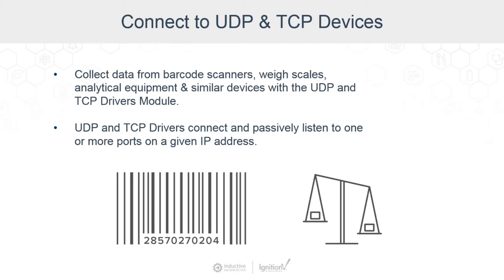Travis, your experience on that? It's important because it's part of integration with all the devices and information you have within a plant, and it's about how to get to them. A lot of weight scales and barcode scanners may be RS-232, or serial, which can be a bit challenging to get access to. There are a lot of ways you can do that. You can put a Moxa serial-to-Ethernet converter in front of it, and then connect to it with the TCP driver, which allows it to get that information to Ignition. It can help for quality systems and just getting more data. It's really about having a driver set that allows us to get to the information that's out there — because there's a whole variety of different devices, different protocols, and different ways that data exists in the plant.